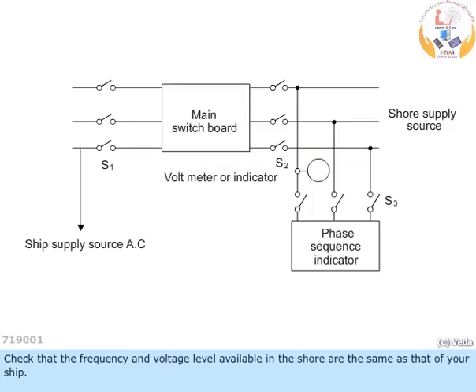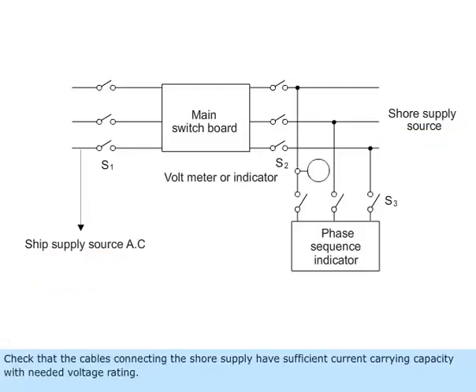Check that the frequency and voltage level available in the shore are the same as that of your ship. Check that the cables connecting the shore supply have sufficient current carrying capacity with needed voltage rating.